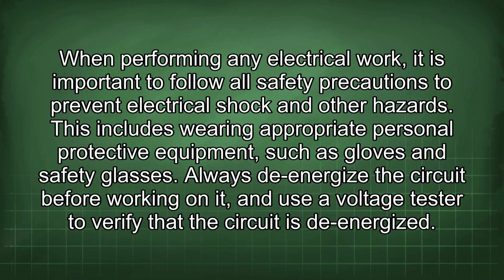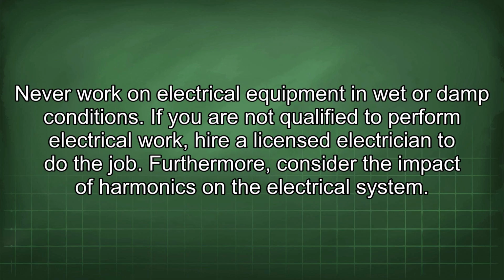Always de-energize the circuit before working on it and use a voltage tester to verify that the circuit is de-energized. Never work on electrical equipment in wet or damp conditions. If you are not qualified to perform electrical work, hire a licensed electrician to do the job.